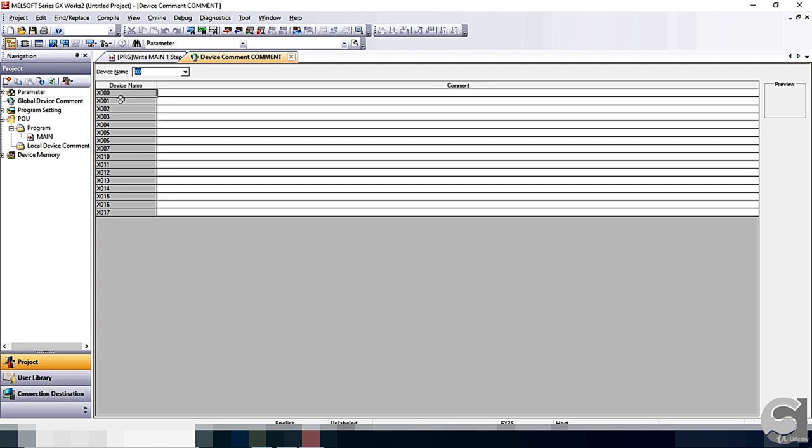For the FX3S, you can see the input is X0 to X17. X0 to X7 is 8-bit. X10 to X17 is another 8-bit. Both of them combined together, you will have 16-bit. That is one word.